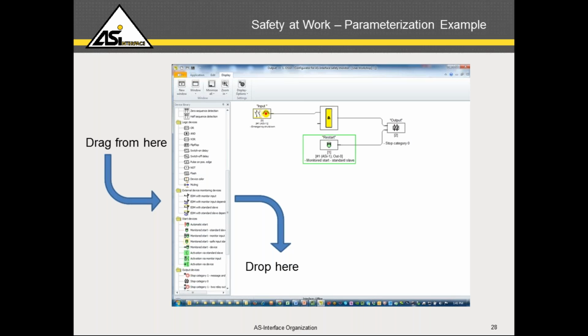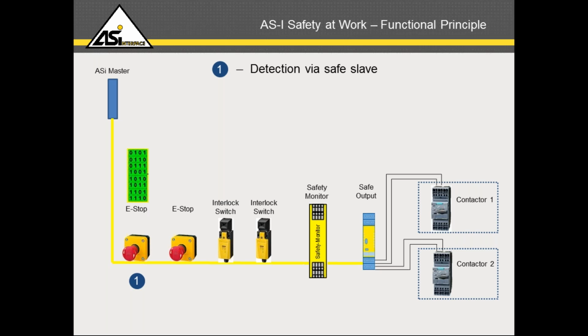The safety monitor then listens on the network to the safety devices, and it makes decisions based on what it hears and then reacts according to this parameterization that's been downloaded into it. So here's how that safe communication works. I said there was a special method of communication. Every AS-i safe slave that's manufactured provides a unique 32-bit code sequence. Since there are over 4 billion possibilities, there's no two devices that are going to have the same code ever.